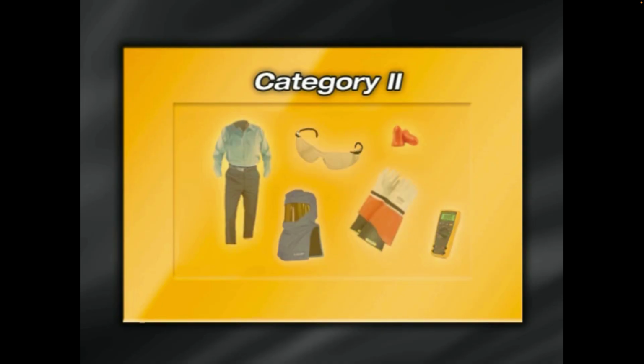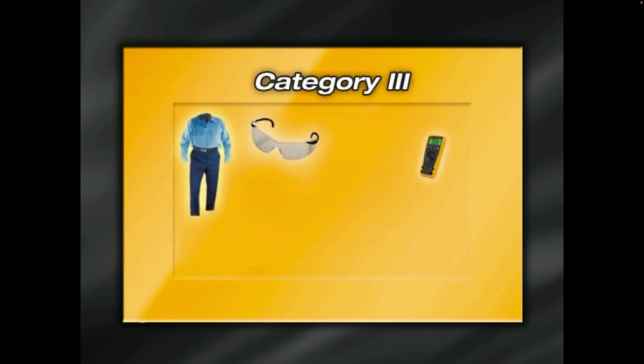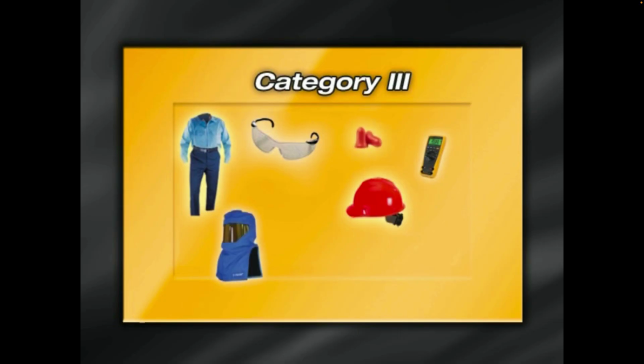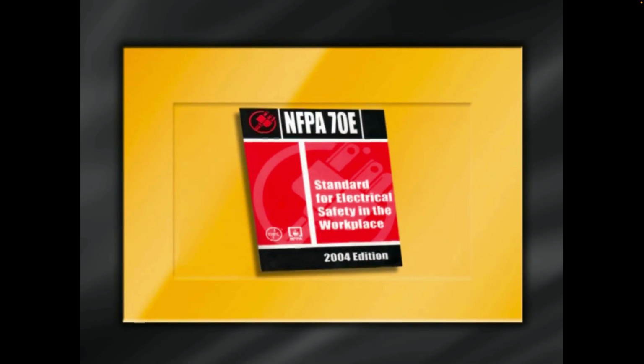Insertion or removal of individual starter buckets from the motor control center takes the hazard to level 3. For this job, you need a hard hat with a flame-resistant liner, switching hood, earplugs, voltage-rated gloves with leather protectors, and work shoes. As you can see, as the risk of your job increases, the protection required by NFPA also increases. Keep in mind that these are general guidelines. Some procedures within Category 2 require greater protection, as described on page 31 in the NFPA 70E manual.